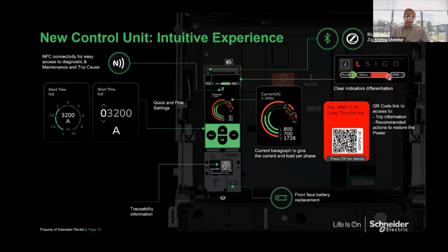This ERMS, as of now, some of the breakers do have, for example, MTZ Micrologic X has got the ERMS feature, but it's optional. You have to add on a software module. Plus, this feature is only activated or deactivated based on human interface. Let's say an operator is in the electrical room, he has to activate this function. Now, since safety is not optional for Schneider Electric, all MTs are active, whether it's A, E, AP or EP type of trip unit, by default comes with the ERMS feature. So ERMS is a standard feature inside the circuit breaker, plus to activate or deactivate is from the front of the trip unit. You open the flap, you can activate. The trip unit display will turn blue, which means it's in the ERMS mode.